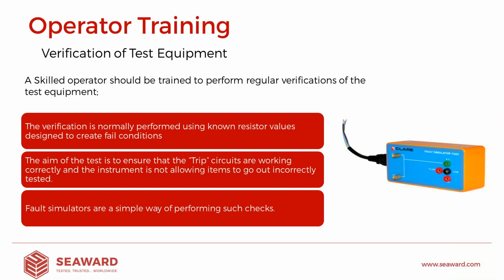So in order to do this, we could use very simply just some known resistors, and they're designed to create a fail condition. So as a good example, I spoke earlier about lighting. We have a 5 milliamp pass fail limit, and we apply 1500 volts to that test. So we apply 1500 volts. We have a resistor that at 1500 volts develops more than 5 milliamps of test current, and therefore what we would expect to see is the tester pick up on that, fail the test, and stop the test safely.